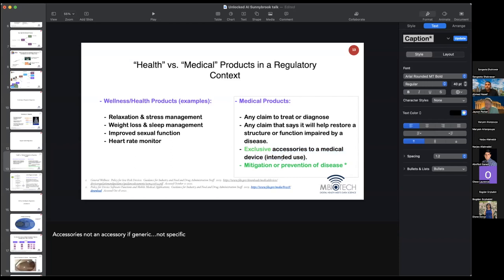But here's where you get into trouble: the mitigation or prevention of disease. Arguably, the shirt I'm wearing right now could be a medical product because it helps with thermal regulation, which allows me to avoid hypothermia — and hypothermia is obviously a clinical condition. So mitigation or prevention of disease exists on a continuum — this is not a categorical variable. How do you sort this out? You're going to have to use hazard analysis. Medical products have an area of ambiguity that is a continuum of risk, specifically around mitigation or prevention of disease.